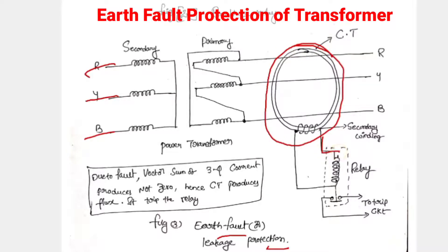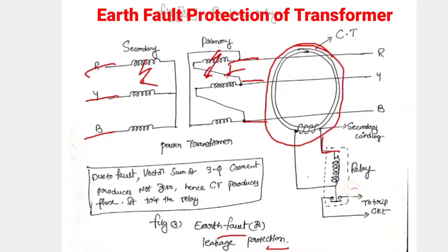It is similar to differential protection. If any fault occurs in the primary winding or secondary winding — whatever the fault may be, including earth fault — the vector sum of the three-phase currents becomes unequal, not zero. Hence, the CT produces a flux, forcing the relay coil to trip. The relay coil is connected to the trip circuit.